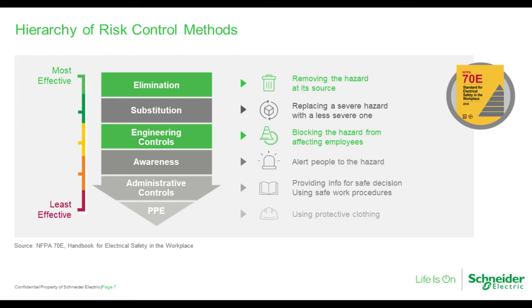Also in that top half of the list, you're going to find engineering controls. And these include options that reduce risk without worker involvement. An example of an engineering control that automatically reduces risk of shock, for instance, would be GFCI protection. Another would be the use of barriers to prevent inadvertent contact. Now, these higher order controls are more effective. They're usually applied at the source, and they're less likely to be affected by human error. The solution you're going to hear about later in this presentation is a higher order control. It's an engineering control that's integrated into the equipment. It can also be used in conjunction with other control methods to establish and maintain an electrically safe work condition.